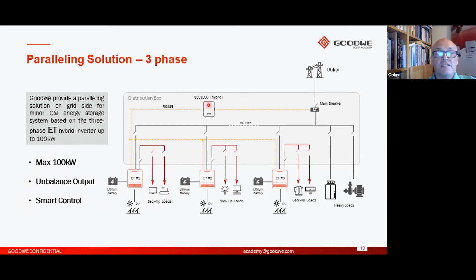Each inverter's backup side is only responsible for the essential loads that it is connected to. As Raj said, the SEC 1000 hybrid piece of equipment here is responsible, when it's on grid, for intelligently controlling the discharge and charge of the batteries across the whole set of ET inverters. When it goes off grid and you lose the grid supply, each inverter supplies power to its local backup supplied loads. On the left here, as we said, it's a maximum of 100 kilowatts because we can have 10 of these in parallel, and we are also able to support unbalanced loads. I'm going to show you something about that a little later. And as we said, smart control is achieved via the hybrid SEC 1000.